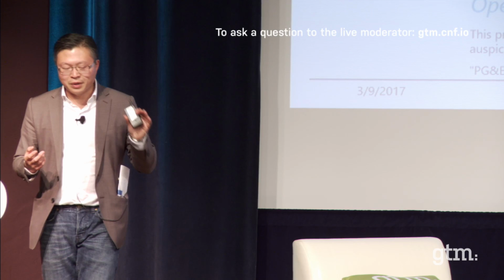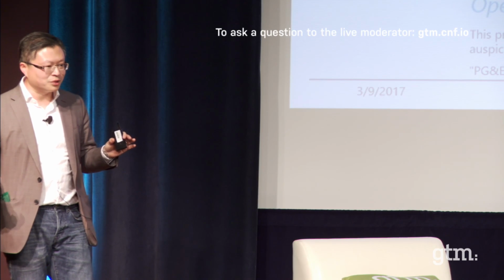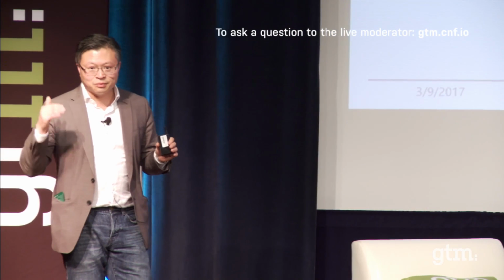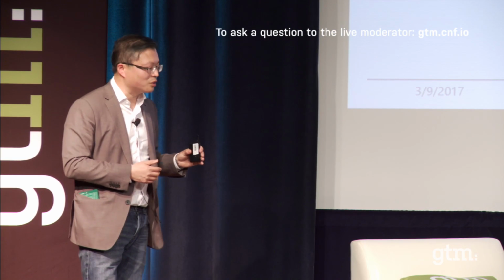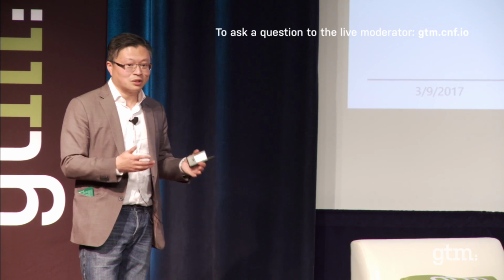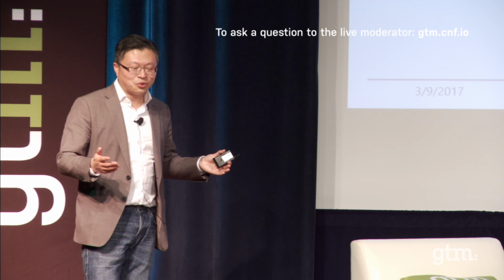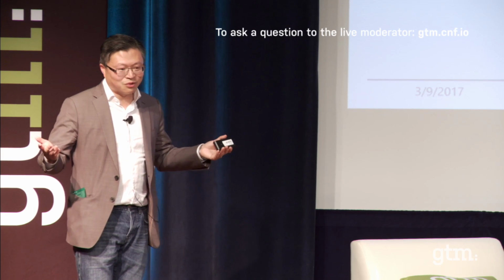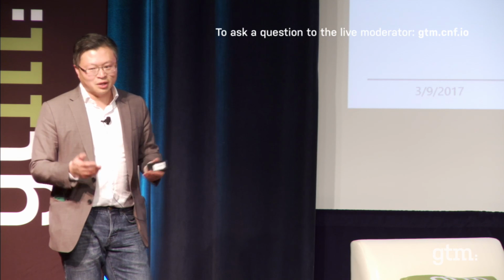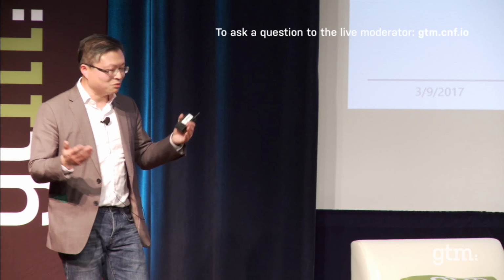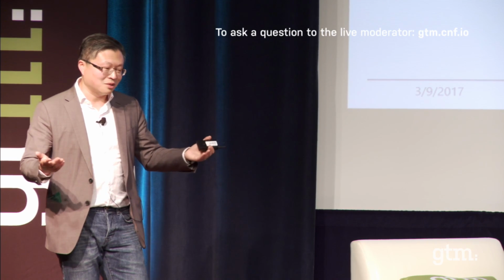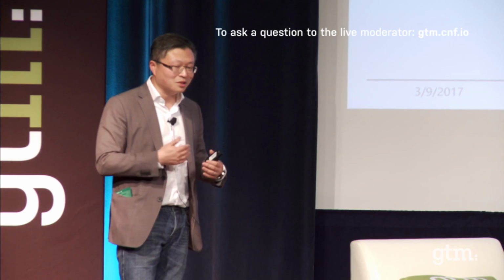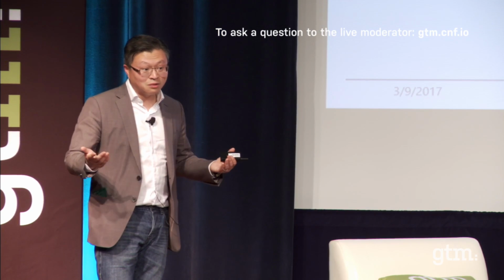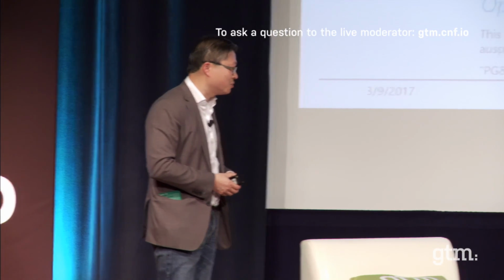Sure, yeah, we take M&V very seriously. We have 2 revenue-grade meters, one at the main circuit breaker of the building, the other at the output of our system, and we take second-by-second data recordings of all those power numbers. So after the fact we can reconstruct exactly what happened during the month, though we've never had to go to that granularity. So if a customer asks whether we really reduced demand, we have historical data second by second that says either we did or we didn't, and we've been pretty successful with that approach.